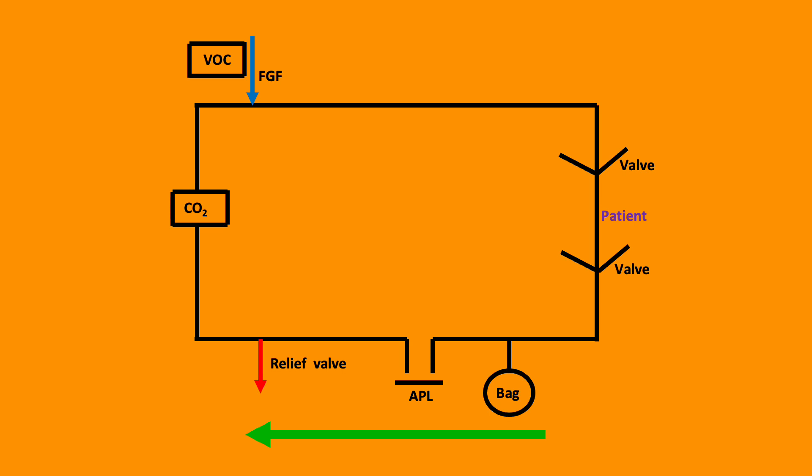If we look at the diagram, we have fresh gas flow input. The patient is positioned between two unidirectional valves. Following the patient, there's a bag to squeeze to allow observation and intermittent positive pressure ventilation, the APL valve, and a relief valve in the event the pressure within the system is too great, which can result in lung trauma. The CO2 removal agent will remove CO2 from the circuit to enable the use of low-flow anesthesia.